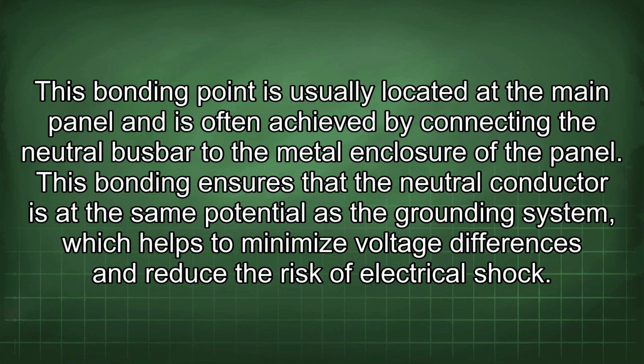This bonding point is usually located at the main panel and is often achieved by connecting the neutral busbar to the metal enclosure of the panel. This bonding ensures that the neutral conductor is at the same potential as the grounding system, which helps to minimize voltage differences and reduce the risk of electrical shock.